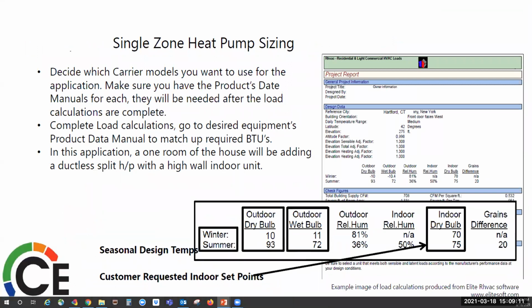We want to, in this example, try to keep our room temperature around 70 to 75 with an outdoor temperature of 10 to 93. And we all know it can get well above or well below these numbers, so just take that into consideration. And don't forget about location, like a bonus room, garage, or high ceilings. Maybe surrounding factors like the windows, good insulation, good doors, good shade. Is this their only source of heating and cooling?